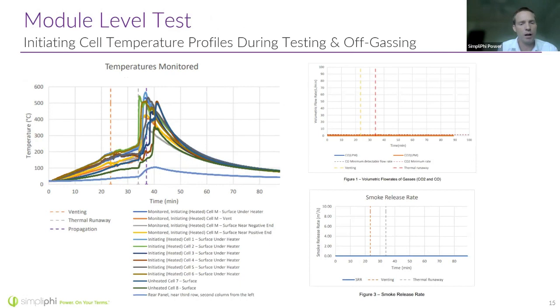So there's, I think, 8 different cells that are being monitored here, as well as different locations inside the battery module. And what you can see if you follow this graph up is it's getting hotter and hotter and hotter inside the battery cells themselves. You see some kind of rough data coming in. That has to do with the off-gassing. So around 200 degrees Celsius, you can see some off-gassing that's occurring here. That off-gassing is actually a rapid reduction in pressure, and so it's accompanied by a slight decrease in temperature. So that's the kind of noise that you're seeing there.